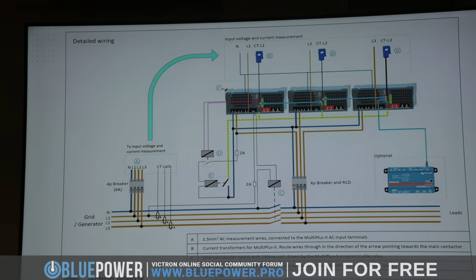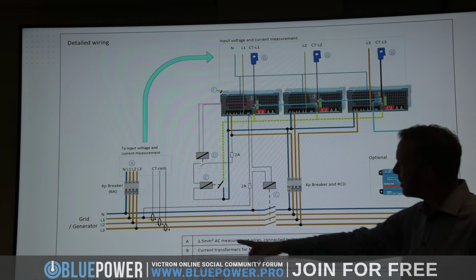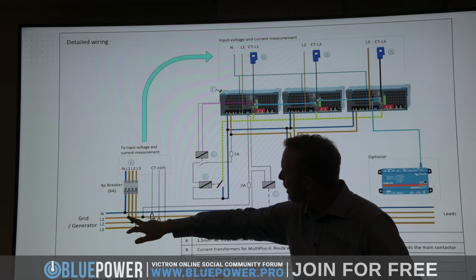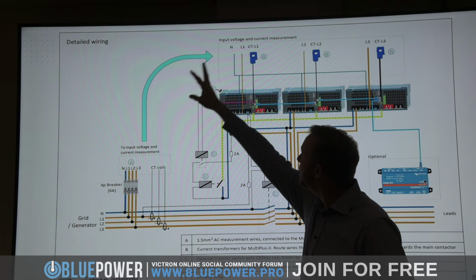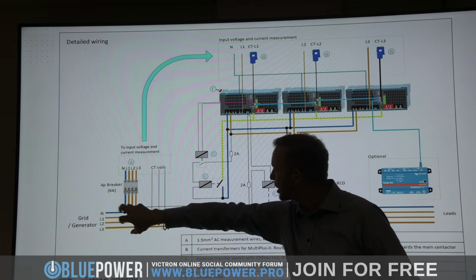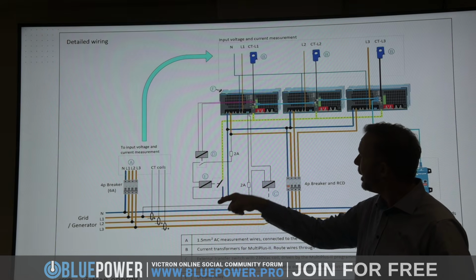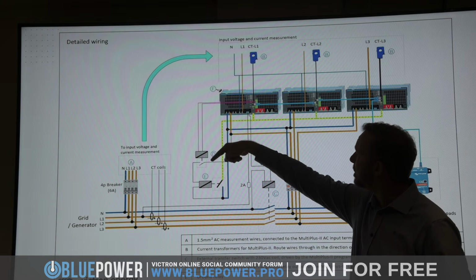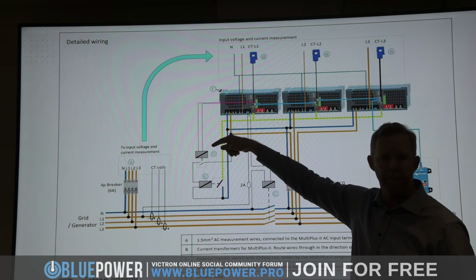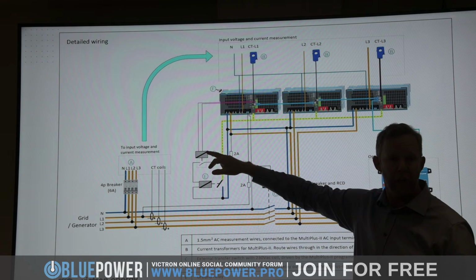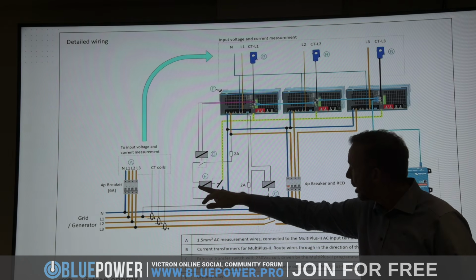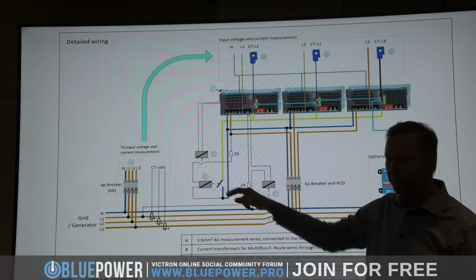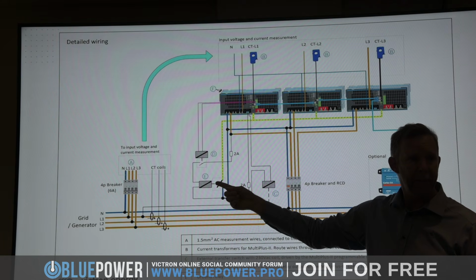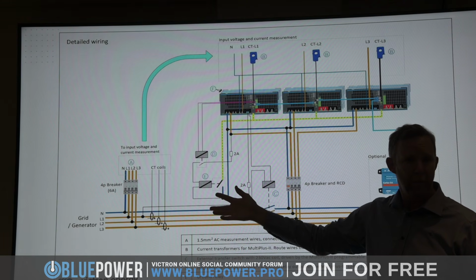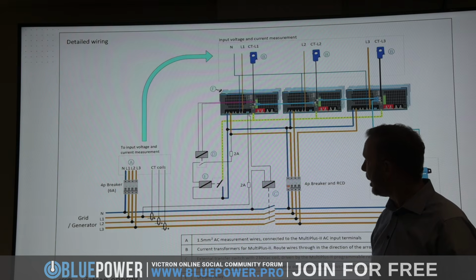So this is from the manual. It gives you an exploded view. There you see the CTs and this very thin voltage measurement for the input, the AC input, to do the voltage sensing from the supply. Then the ground relay. We use the internal ground relay mechanism, which is 200 milliamps, so here you need a helper relay. It operates on 200 milliamps and switches another, more high-powered relay, because the bigger the power, the bigger the ground relay must be. That's why that needs to be there.